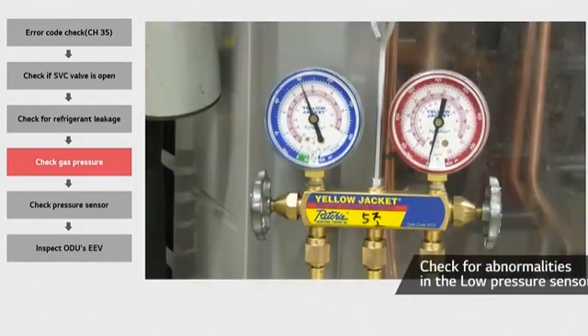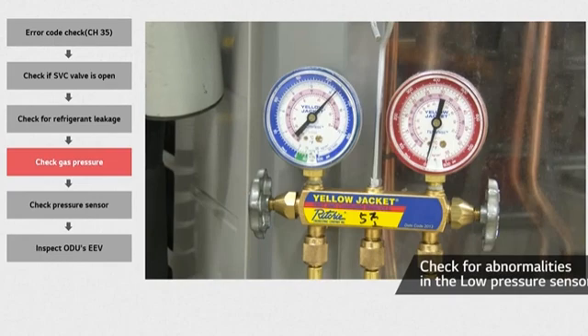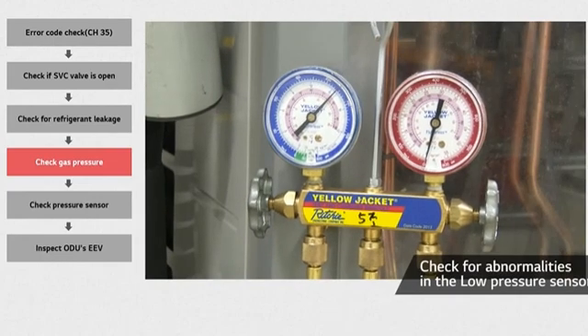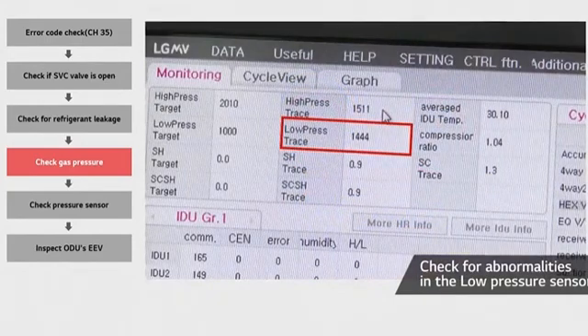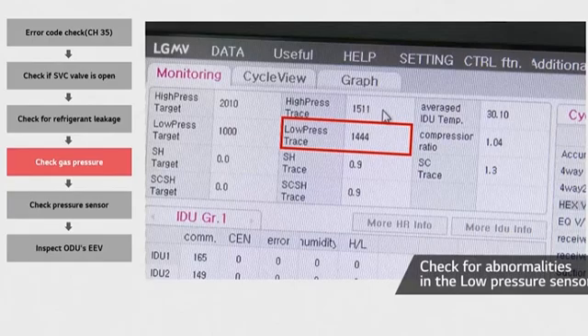When measuring the refrigerant pressure, use a manifold gauge. As the needle rises, you can check the increase in pressure. Connect the blue line with the low pressure valve and the red one with the high pressure valve. Then, compare the refrigerant pressure values from the LGMV and the one from the manifold gauge. If the values differ a lot from each other, you can assume the sensor to be damaged.